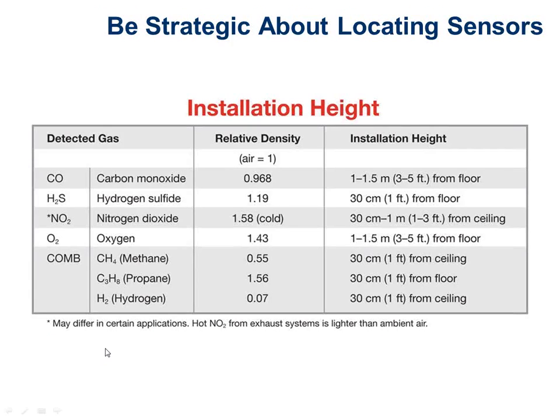Well, this slide's a little bit confusing because we have the cold here, but I didn't put the hot one on here. When nitrogen dioxide is hot, like coming out of a diesel engine, it actually rises quickly and it's, quote unquote, lighter than air. So we typically measure nitrogen dioxide below the ceiling level. That's why they're telling you that here on the right. I should have had 2 rows on here, one for cold and one for hot nitrogen dioxide. So I do apologize for that. There's a note on the bottom there, but I realize no one's going to read the note. Hot NO2 gas from exhaust systems is lighter than ambient air. Right? So normally we're measuring it below the ceiling, which is why it says that.